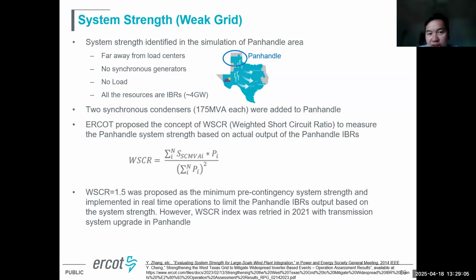We tried system strength studies, even in real time. There's an area called Panhandle, far from the load center at the edge of the system, with no synchronous machines, no load, and all resources there are IBRs—it was 4 gigawatts at the time, now more. We knew there was a system strength issue, so we added two synchronous condensers, each 175 MVA, but we still found the system was weak.